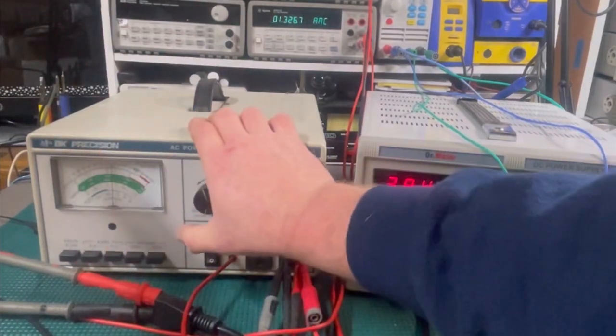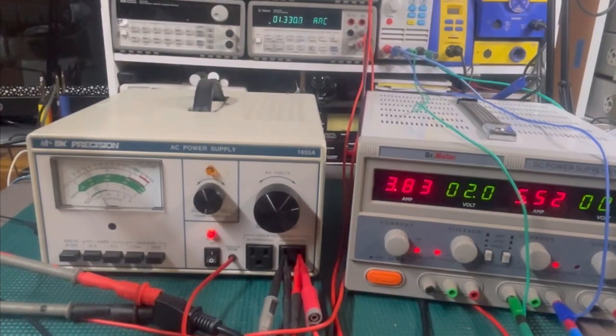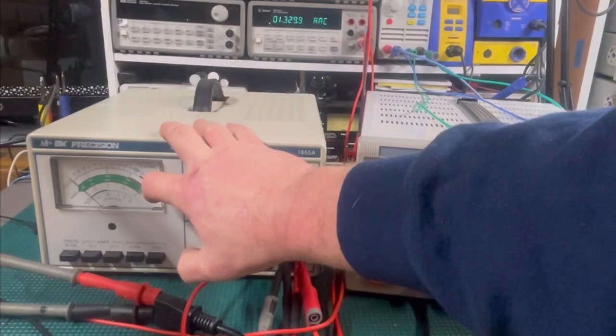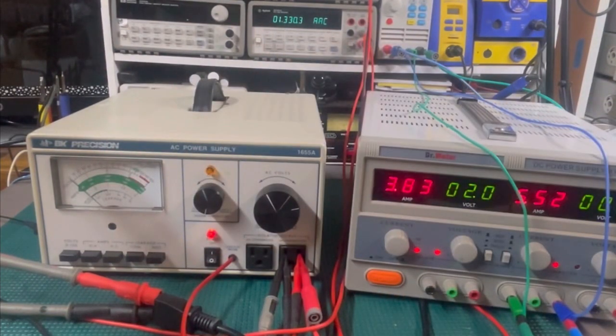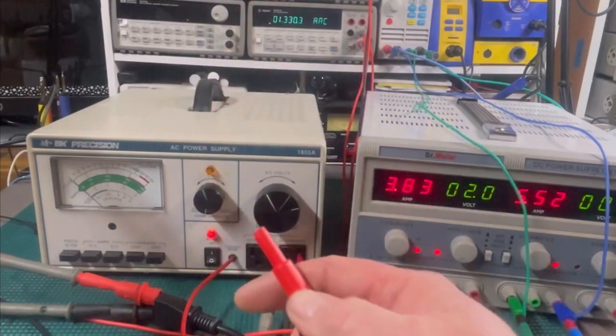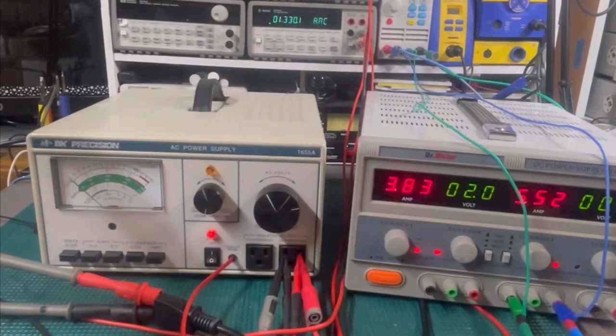So despite what I said, it's kind of finicky there as we switch it. But for the most part, once you get a good reading out of it, we're spot on. That's bang on, pretty much. The amperages are good. It's just the voltage isn't working. And because this voltage isn't working correctly, I assume... well, no, actually, the leakage should be working correctly as well, because this guy doesn't know that the gauge is off. So the only thing that's off is the 120 AC voltage coming out of this. I think as far as our leakage, that's bang on too.